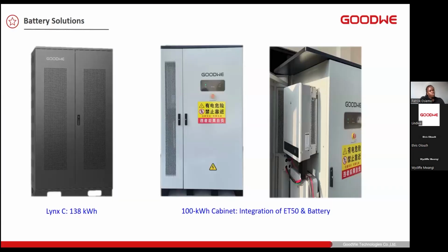Battery solutions in GoodWe can come in terms of IP rating. So if you want to do indoor, then you can choose the Lynx C. If you want to do outdoor installation, then we have a containerized solution, which is a 50 kVA rated hybrid inverter. And on the right side, you have a battery panel, which will hold up to 100 kilowatt hour of battery bank. This is expandable. The ET is expandable for the containerized solution as well. So you can do 3 of the ET50s to expand on the AC side. If you want to expand on the battery side, you can do it in steps, in banks of 100 kilowatt hour, and extend your battery storage.